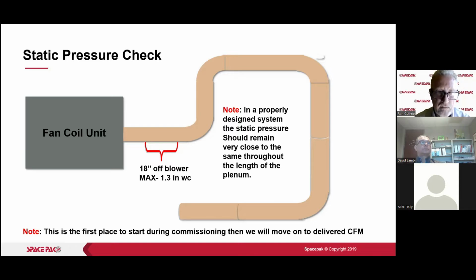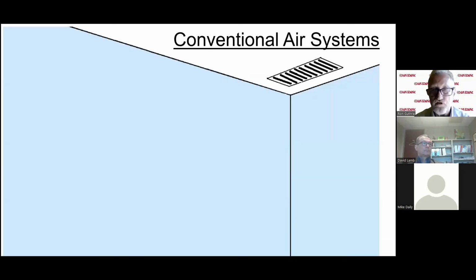I would always check it with a manometer as well. You could have a kink in the plastic tubing that goes from the pitot tube coming out of the unit at the outlet of the unit. That is hooked by plastic tubing into the port on the board that measures the pressure, right? So always measure your pressure anyway.